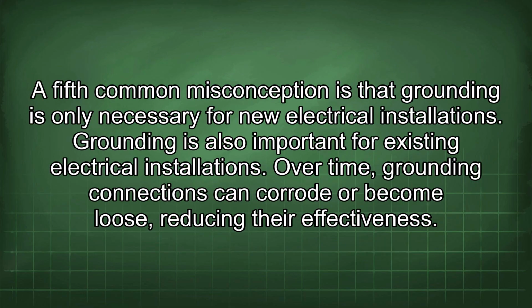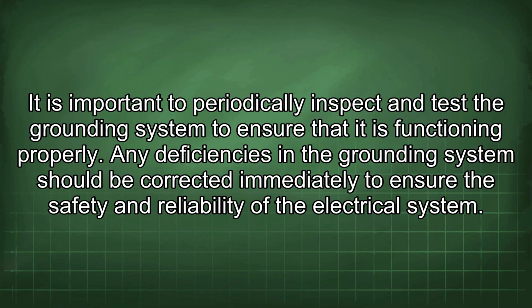A fifth common misconception is that grounding is only necessary for new electrical installations. Grounding is also important for existing electrical installations. Over time, grounding connections can corrode or become loose, reducing their effectiveness. It is important to periodically inspect and test the grounding system to ensure that it is functioning properly. Any deficiencies in the grounding system should be corrected immediately to ensure the safety and reliability of the electrical system.